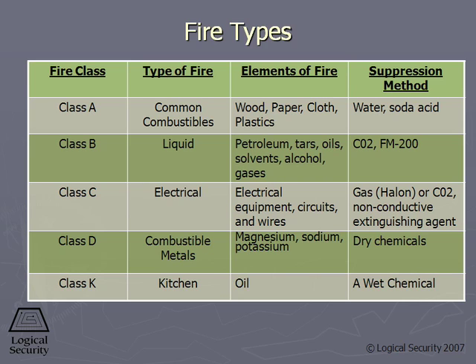A Class B fire is a liquid fire. These are flammable liquids such as petroleum, tars, oils, solvents, alcohol, and very often the most popular suppressant for these are gases. We see CO2 and FM200 both being suppressants for the Class B type of fire. Again, these are both gases. One of them, of course, CO2, is hazardous to humans, and FM200 is an approved halon replacement.